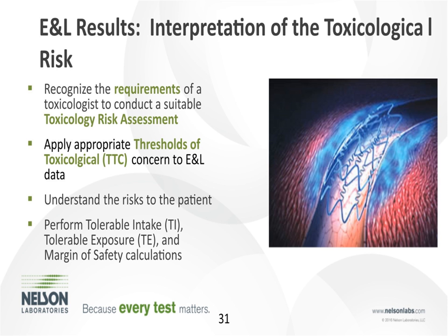And that is so we know that a suitable extractable leachable study was performed, that the appropriate thresholds of toxicological concern are applied, that all of the risks to the patients were evaluated, and that the calculations that need to be performed are done correctly. And I'll be going over those calculations here in just a few slides.